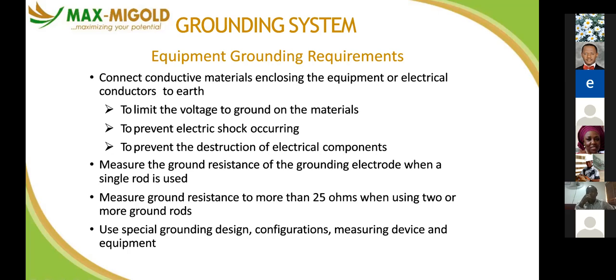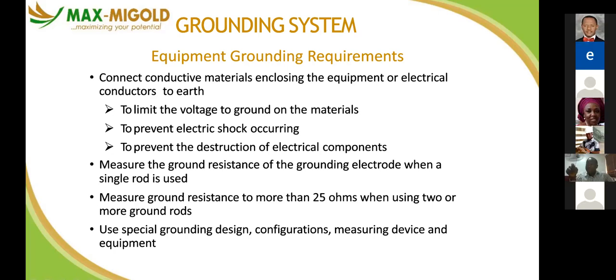You may not necessarily earth it because it's connected to the generator. There is an installation there to your generator, right? If you use a galvanized pipe, the continuity of your generator extends to that overhead tank. But if it's not a galvanized pipe and you use a PVC pipe, you don't need to earth it. That's no link. When I'm using tall steel stanchions to hold my tank, do I need to earth it? If there is anything that has to do with electricity to your tank, you need to earth it. It doesn't cost much. You can just run a wire to where you earth your generator.